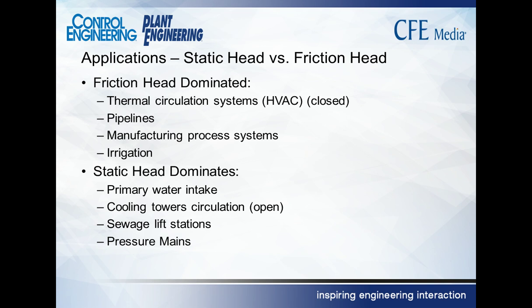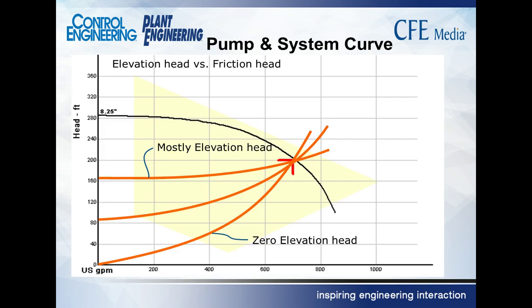Static head dominated systems: primary water intake, where you're pumping it out of a lake or a river, pumping it up into a reservoir. Cooling tower is a good example. They take the liquid out of the bottom of the cooling tower, pump it up into the top, dump it out. The only thing it does is lift the water. Sewage lift stations are a classic example. Pressure mains, it's not an elevation, but there's still a static head because you'd have to overcome the pressure in the main before you can pump anything into it. So they also fit into that high static head category.